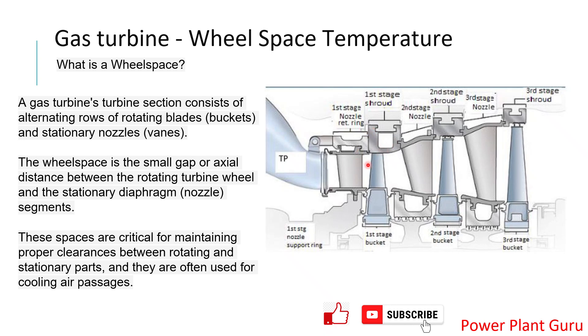The wheel space is the void space between the static and rotating blades, and it is very important. This gap should be kept to a minimum to avoid excessive losses. However, if it is too close, during thermal elongation the parts may rub against each other, which can cause catastrophic failure in the turbine. So you must avoid both excessive space and insufficient gap.